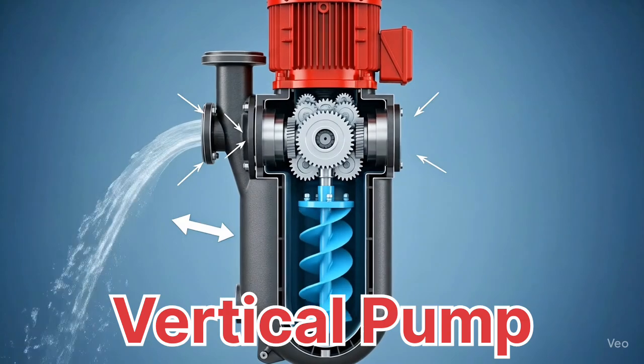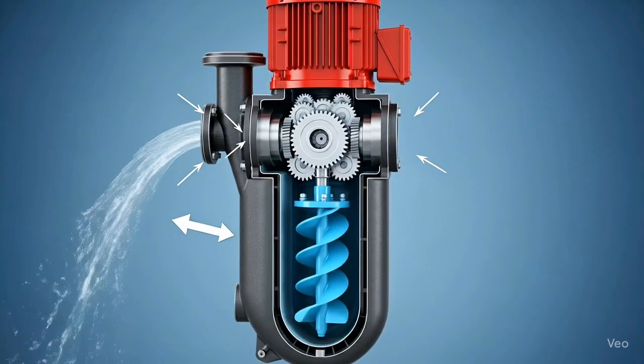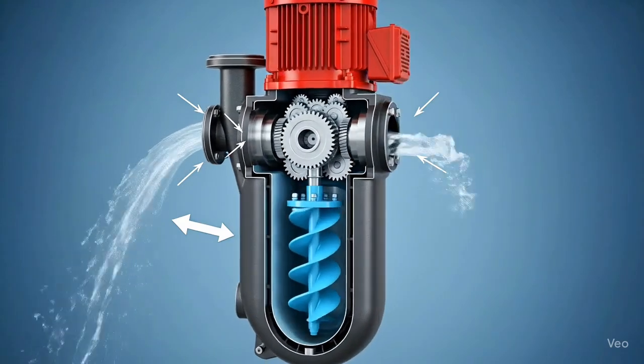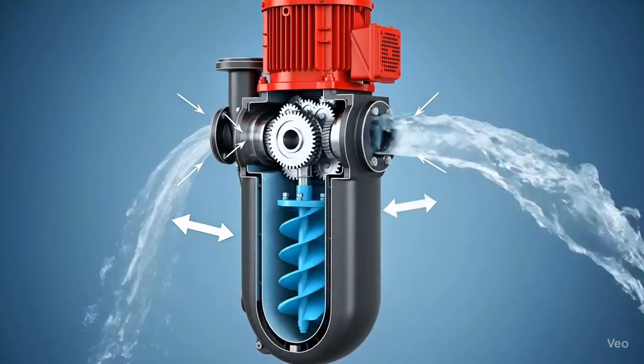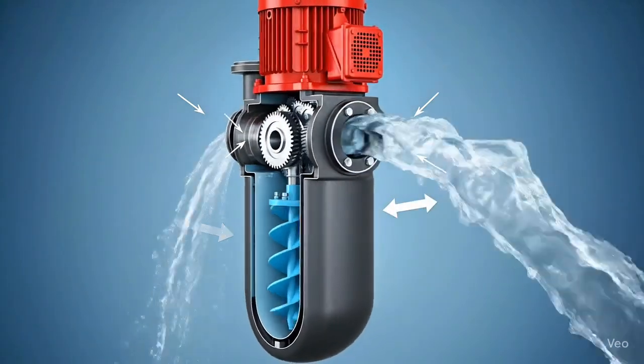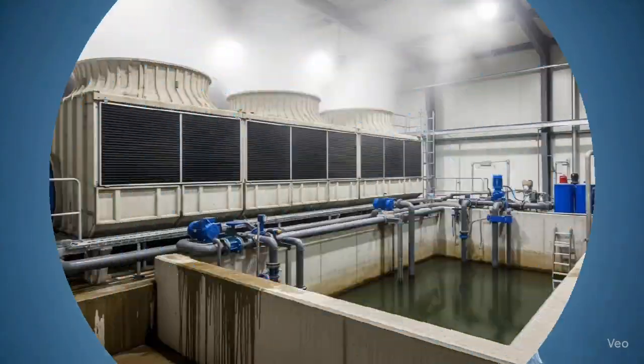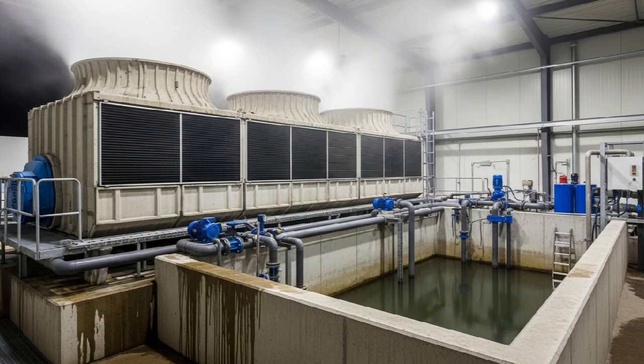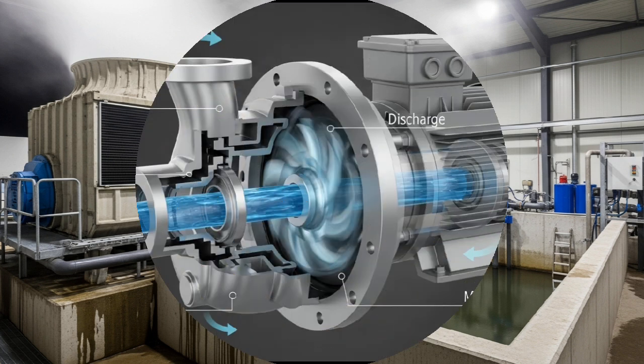Let's look at vertical pumps. The motor and shaft are positioned vertically. Usually installed inside a sump or tank. Requires less floor space but more headroom. Many times, no priming is needed because the pump is submerged in liquid.